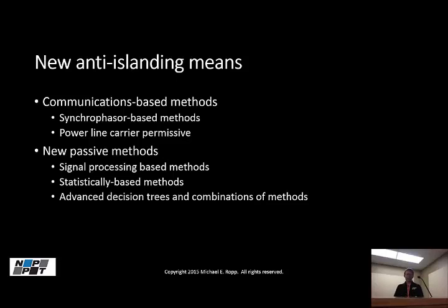The other communications-based method that I've got up here is based on synchrophasors. I'm going to assume that most of us are at least tangentially aware of what a synchrophasor is. You know, a phasor is just a specific voltage measurement, right? Angle and magnitude. Or it could be a current measurement as well. All a synchrophasor is doing is taking a bunch of phasor measurements from different places and then putting a GPS timestamp on them so that we know exactly, this measurement was made at the same time as this measurement. We can time align them and get a picture of what the system looks like, all at one moment in time.